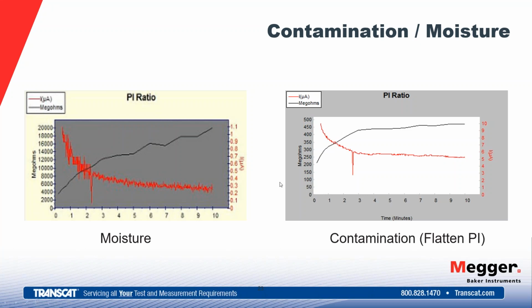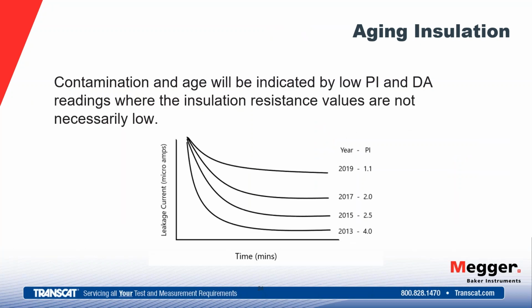It could also be contamination, as we see on the right, not so much moisture, but the flattening of this curve is indicative of contamination. Basically, we would see this insulation continue polarizing if that contamination wasn't there, and the contamination holds it up. Again, those parallel paths to ground, so the current stays high there, even though the insulation may be polarizing. In the PI, we also see the effects of aging. Contamination and age will be indicated by low PI or DA readings, where the insulation resistance values are not necessarily low.